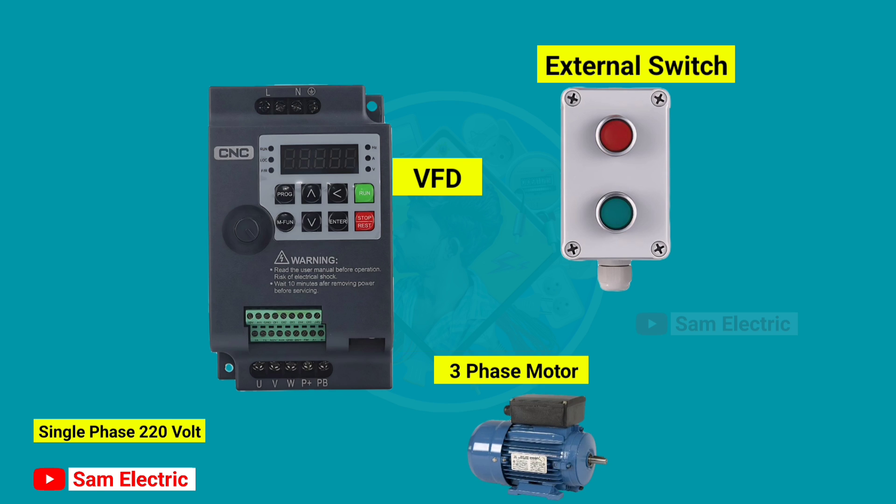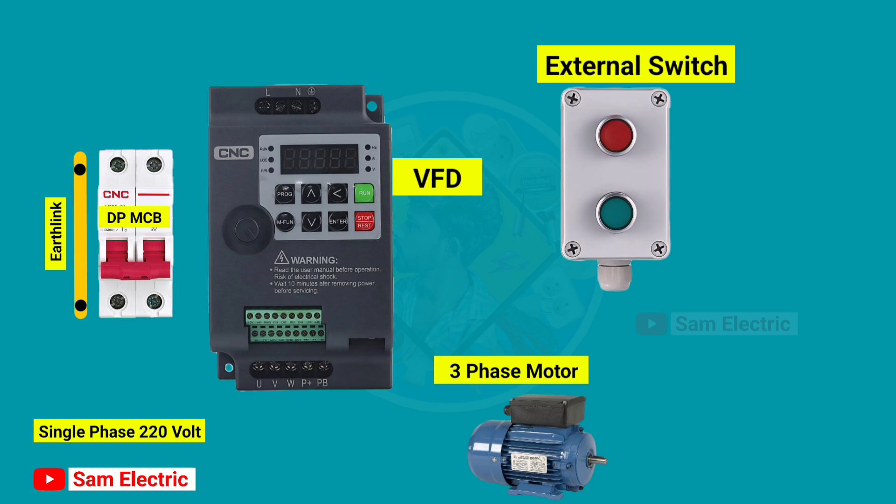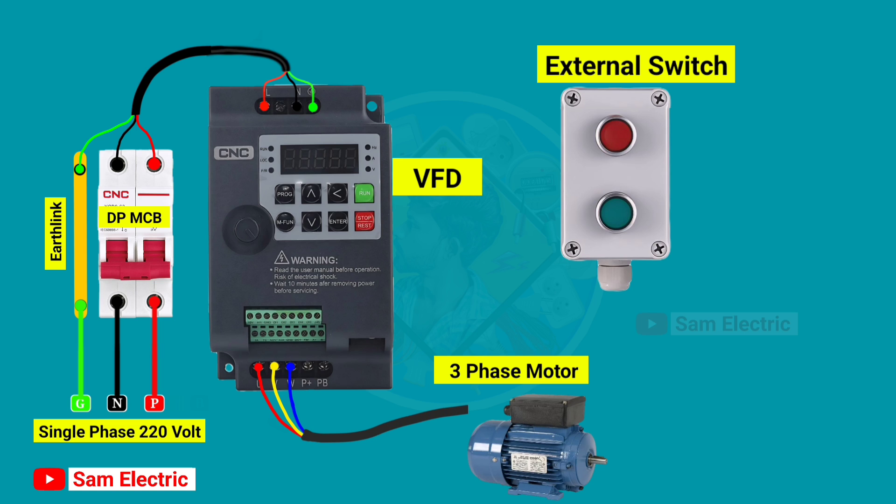First, we have to connect 220V input to the VFD. For that, I am using a DP MCB and an Earthlink. Connect phase and neutral wire in the MCB and earth wire in the Earthlink. Then connect the output of the MCB to the VFD, and connect the VFD output to the motor. Power wiring is completed.